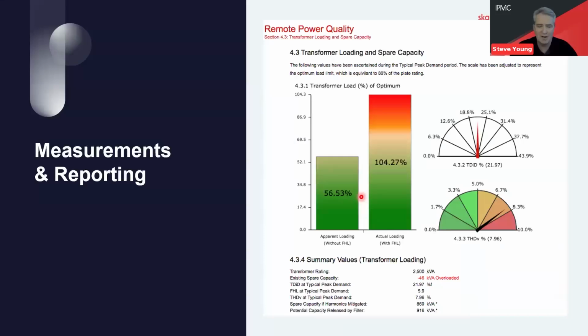So once we've got that, reports can follow all different kinds of formats, but hopefully they're going to tip their hat to some of the things that we've learned about in today's presentation. Of course, kVA demand, but also harmonic content. For instance, the left-hand bar chart here shows the loading versus the transformer optimum limit without any consideration for harmonics. But the right-hand side one shows it with due consideration to that harmonic loss factor.